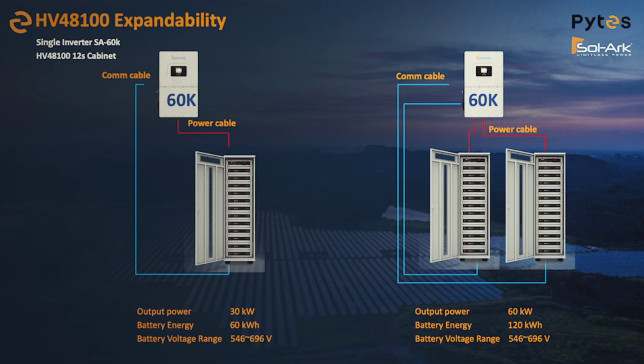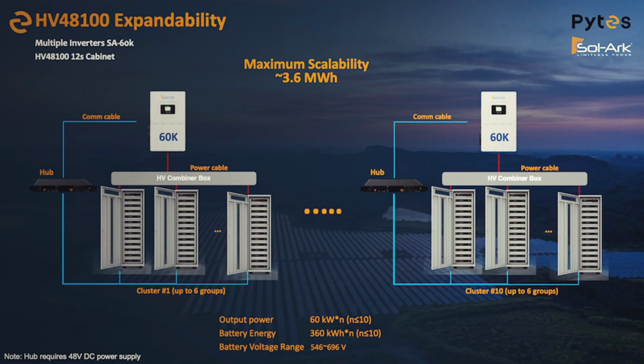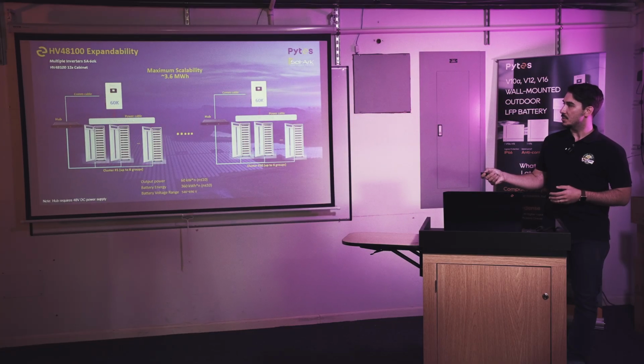That same concept holds true for the 60K. The only difference is usually we're going to use the 12 battery cabinet instead of the 8, so we can get that voltage up a little bit higher. And then of course you can do more than just 2 cabinets, right? With both 30K and 60K. This example is 60K specific. When we get past that 1-to-1 or 2-to-1 ratio, we need a couple accessories. Now we've run out of battery inputs on the inverter. We need to bring all the batteries to a combiner box and actually connect them in parallel. And then usually you have just a single communication cable from the inverter to our hub accessory, which is just an inexpensive communications management device. So all the batteries are communicating with the hub, and then it's the hub that's communicating with the inverter.